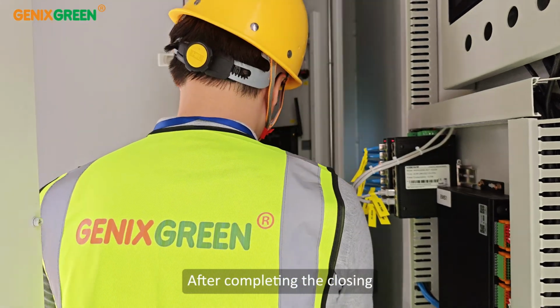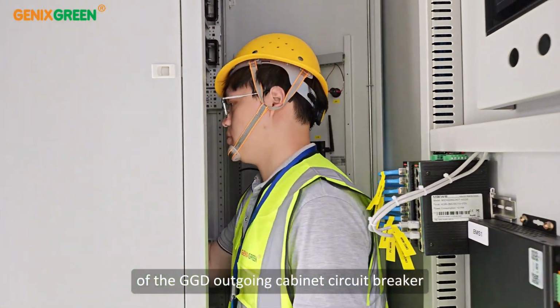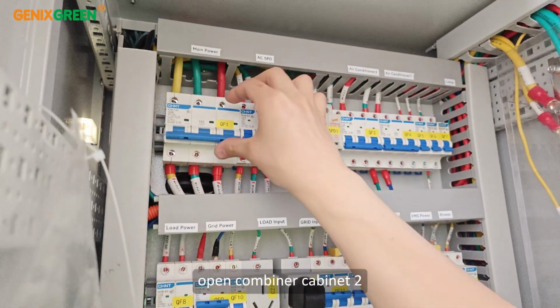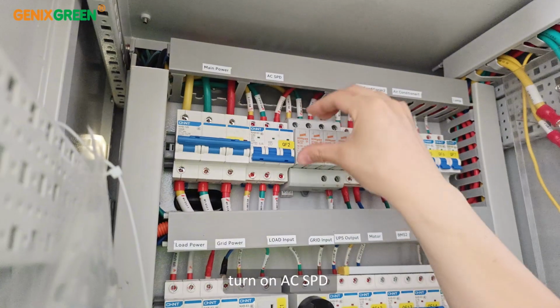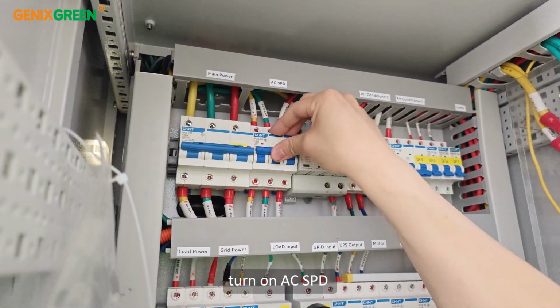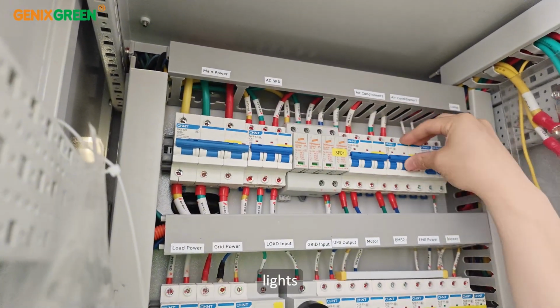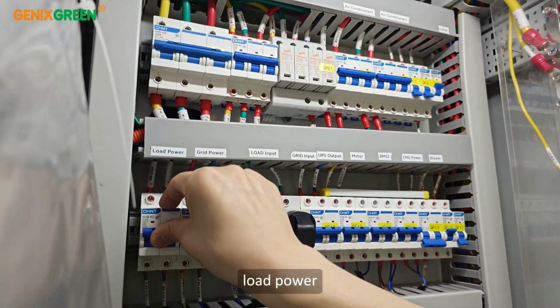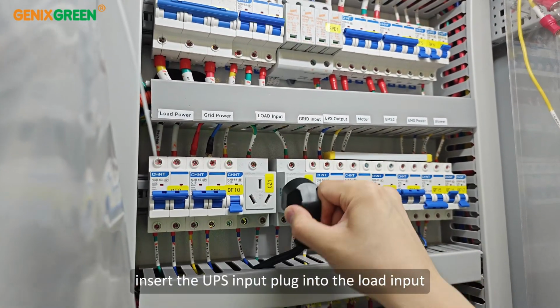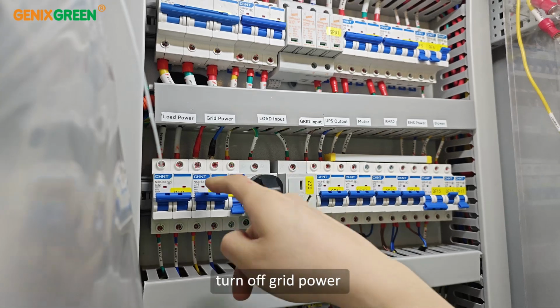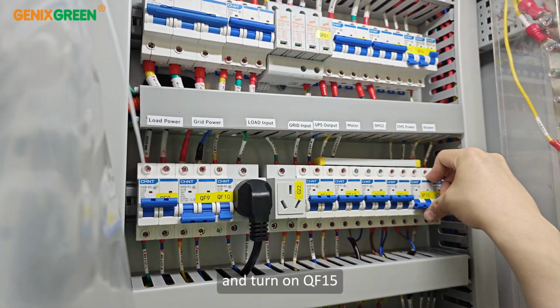After completing the closing of the GGD outgoing cabinet circuit breaker, open combiner cabinet 2, turn on the main power supply, turn on AC SPD. Turn on the air conditioner, lights, load power. Insert the UPS input plug into the load input. Turn off grid power. And turn on QF15.